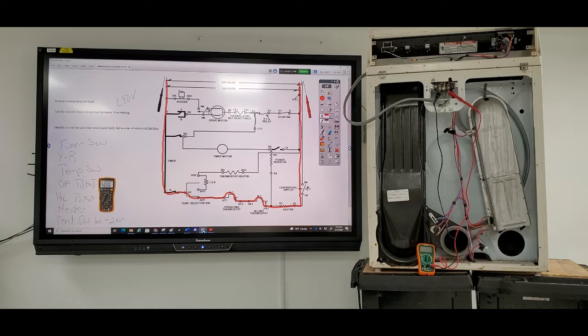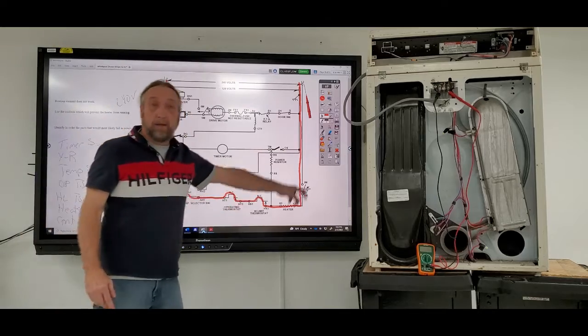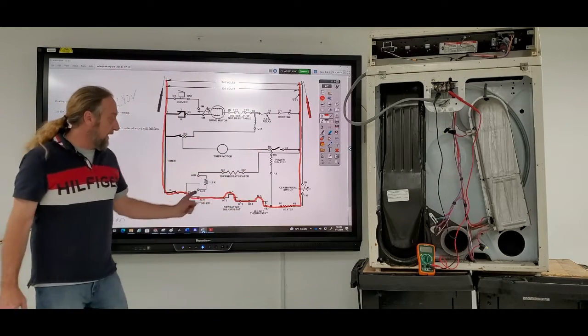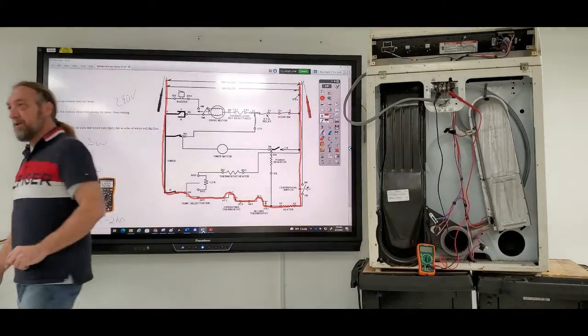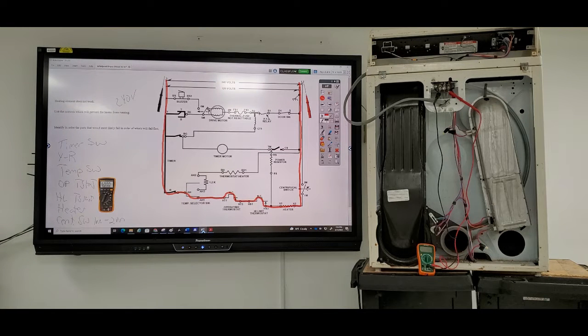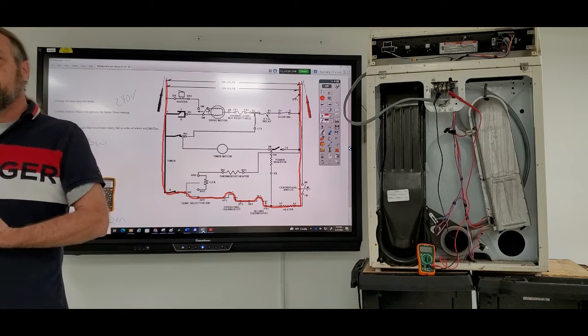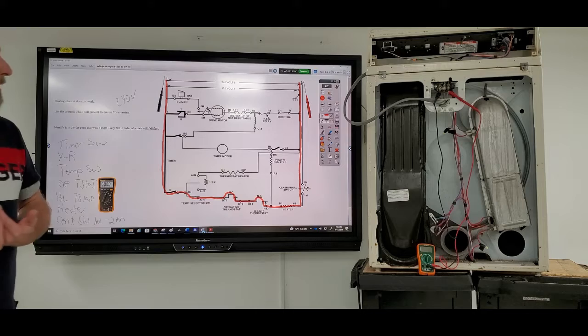Okay, so now we've identified the circuit. We looked at the line we drew, and everything in that line that sends power to the heater is something we need to test. So what's the very next test we need to do? Put a meter lead on H1 and a meter lead on H2 and see if you have 240.